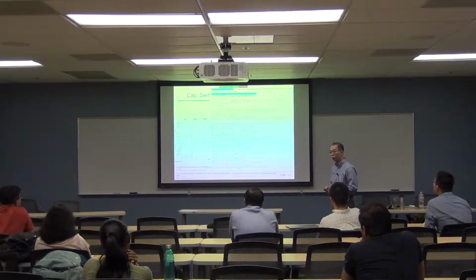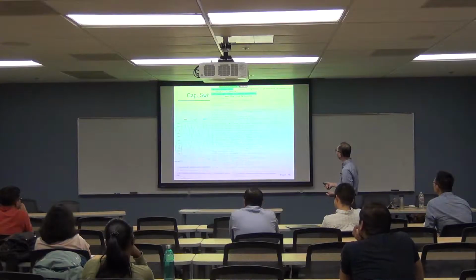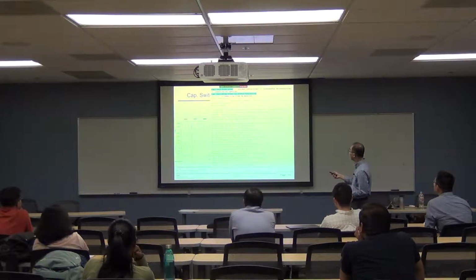And then it looked into capacitor unit health conditions - remember there are two units. If the capacitor is energized properly, both units have to come online by the same amount. It estimates that each phase supply contributes about 2200 kVAR, 2200 kVAR, 2200 kVAR, and the total is about 6640 kVAR. It says the increase is balanced.